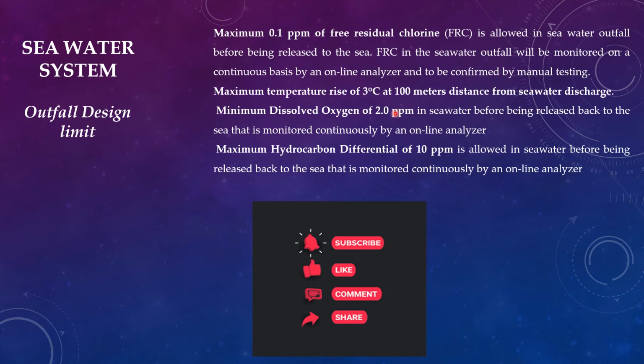Minimum dissolved oxygen should be 2 ppm in the seawater before being released back to the sea. That is monitored continuously by an online analyzer. It should not affect the marine growth. And a maximum hydrocarbon differential of 10 ppm is allowed in seawater before being released back to the sea. That is monitored continuously by an online analyzer. If there is any hydrocarbon contamination in the seawater cooler or heat exchanger, the value should be less than 10 ppm, and only then should it be let out to the seawater outfall.